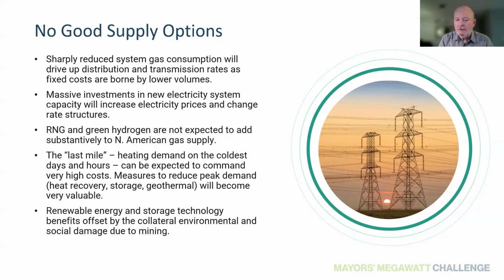So anything you can do to reduce peak demand, especially heat recovery ventilation, exhaust air heat recovery, even if it looks expensive and the payback doesn't look good right now, it's going to pay dividends once we become a winter-peaking system, which is going to happen within the next decade. Anything we can do to reduce demand, thermal storage, geothermal, all those things will become substantively higher value, better payback, better returns than they are today. Those are where we should be thinking on a future basis: future-proofing, risk-proofing, and reducing peak demand will be really important.